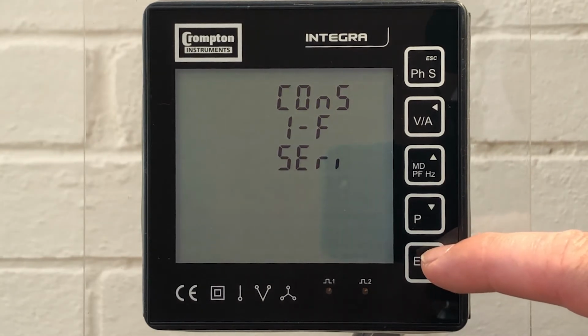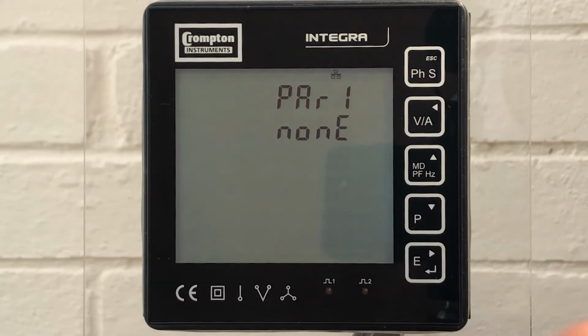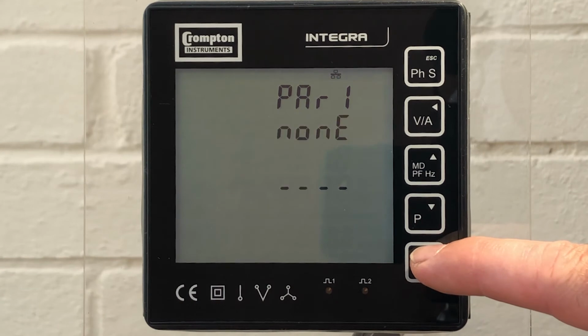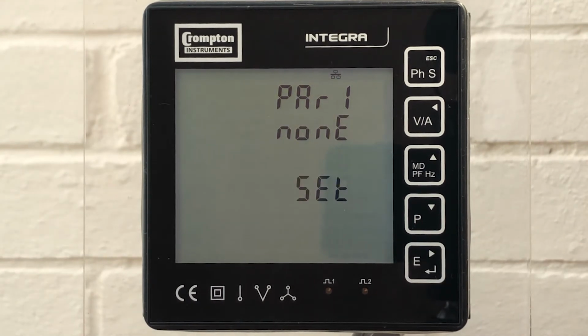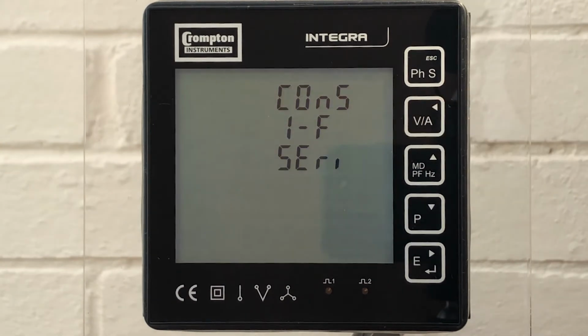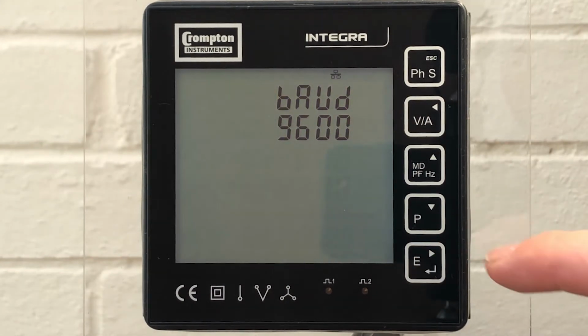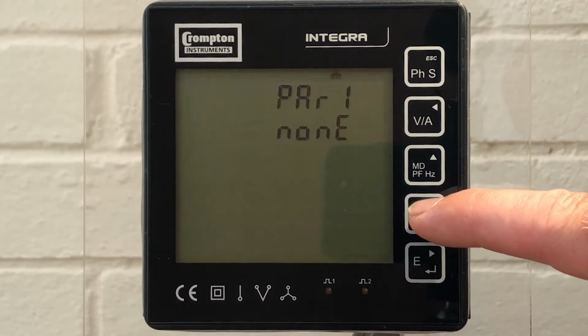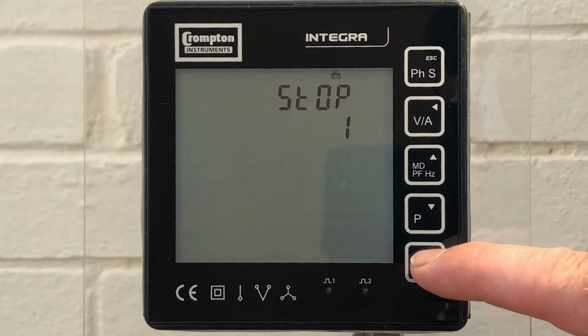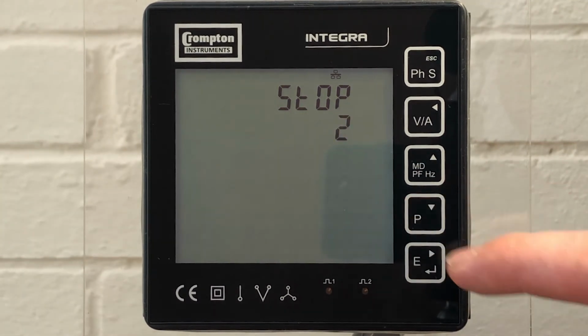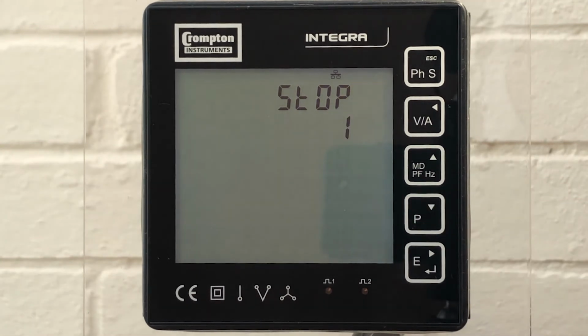Escape back to this screen, hold the E button to go back in, press the arrow down. Now we can set our parity. Available options are none, even or odd. We'll set ours at none by pressing the E button and escape back out with the VA button to then go back into the communications and arrow down to our next communication setting, which is stop bits. Available options on stop bits are 1 or 2. We'll hold E to save this as 1 on this occasion.